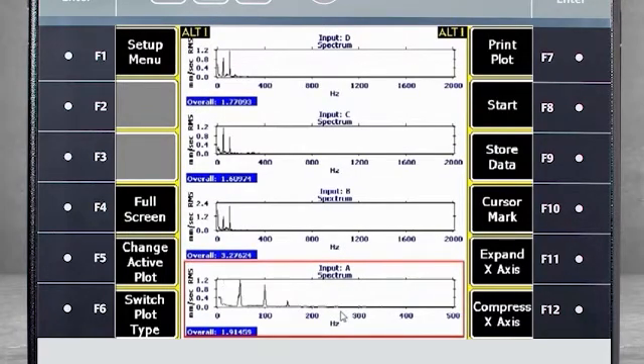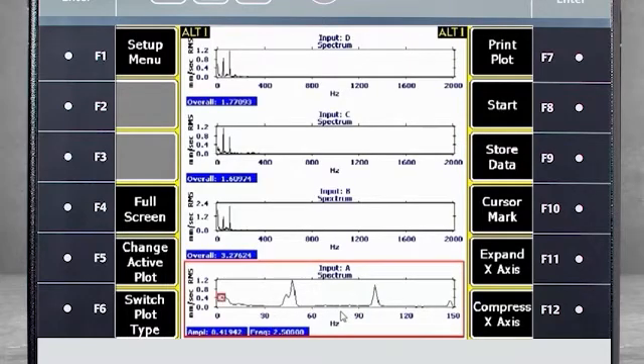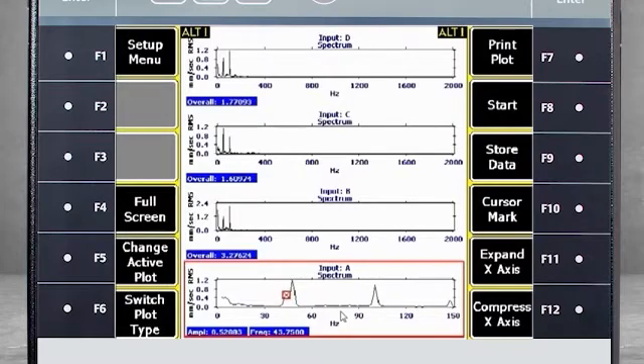When I expand the peak, you see an imbalance value, but that value is actually made up of multiple peaks. This is caused by the varying speed, and causes the amplitudes to be incorrect.